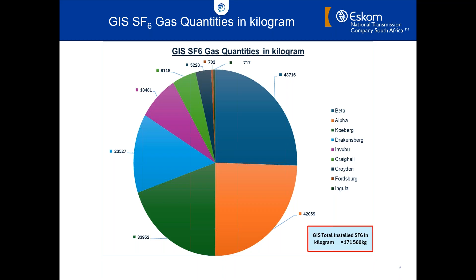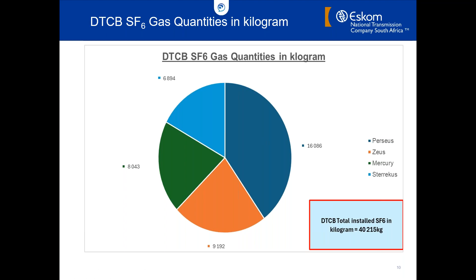We can go around them. Then for Alpha, it's 9 bays, and they carry on until you get to the smaller stations. Fordsburg and Ingula have only got 2 bays. When it comes to the dead tank circuit breakers, from the biggest to the smallest, we've got 7 bays and 4, 4, and 3. So that gives you an indication that one of the phases of a dead tank circuit breaker has in the vicinity of 760 kilograms of SF6 gas. So it's quite a lot of gas, taking into consideration the global warming effect of 23,000 times that of 1 kg of CO2. This has quite a big impact on the atmosphere.